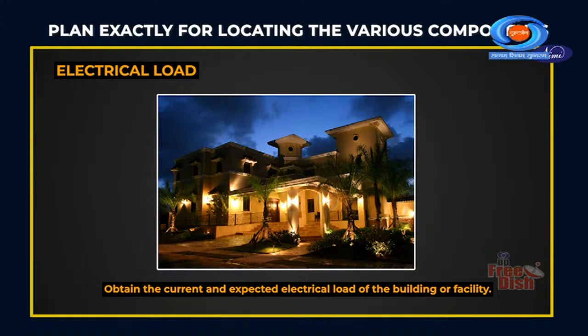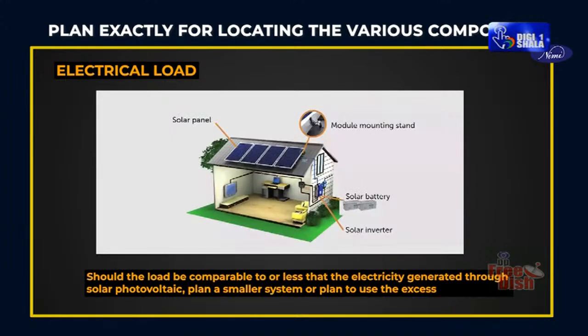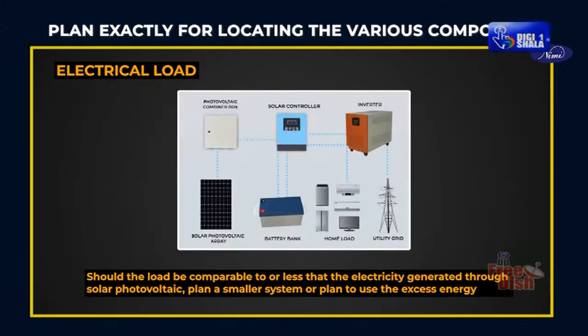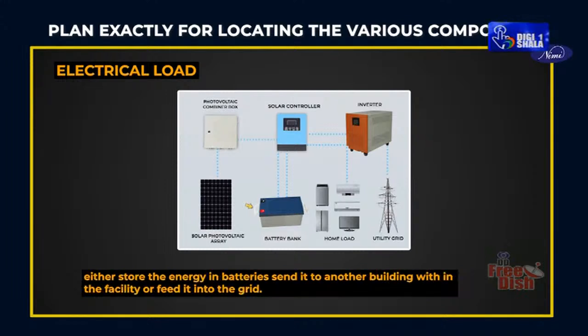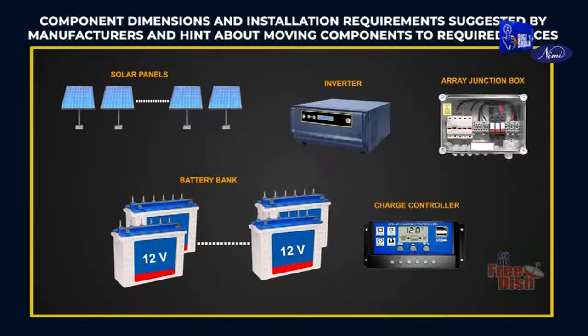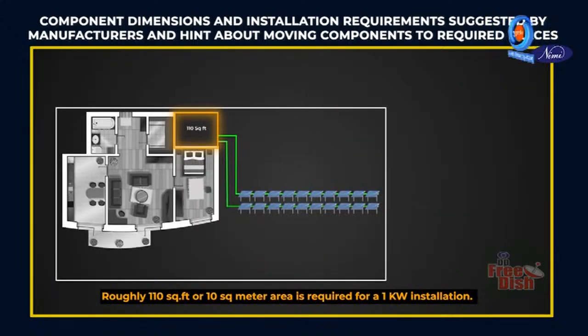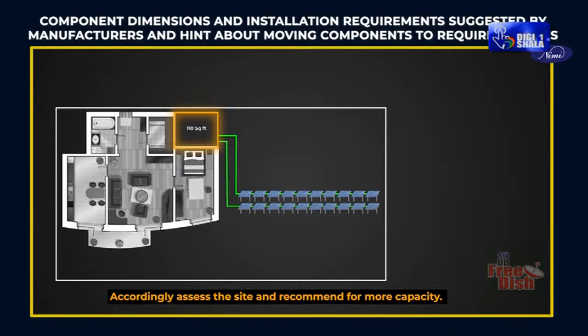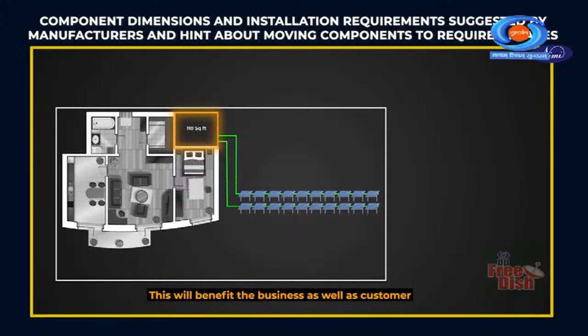Electrical load. Obtain the current and expected electrical load of the building or facility. Should the load be comparable to or less than the electricity generated through solar photovoltaic, plan a smaller system or plan to use the excess energy, either store the energy in batteries, send it to another building within the facility or feed it into the grid. Check component dimensions and installation requirements suggested by manufacturers, and plan how to move components to the required places. Roughly 110 square feet or 10 square meters of area is required for a 1 kilowatt installation. Accordingly, assess the site and recommend more capacity. This will benefit the business as well as the customer.